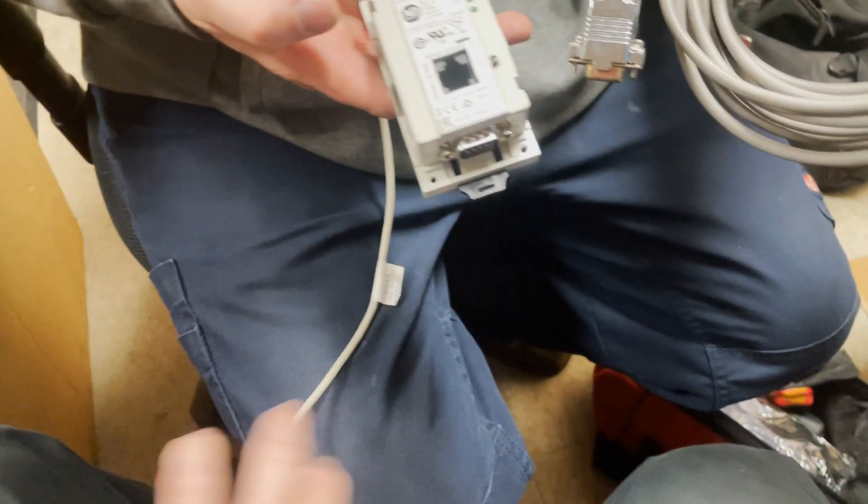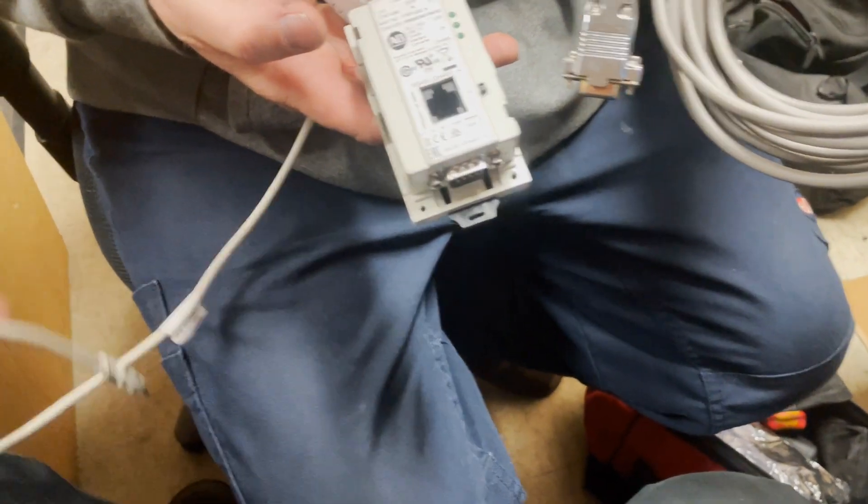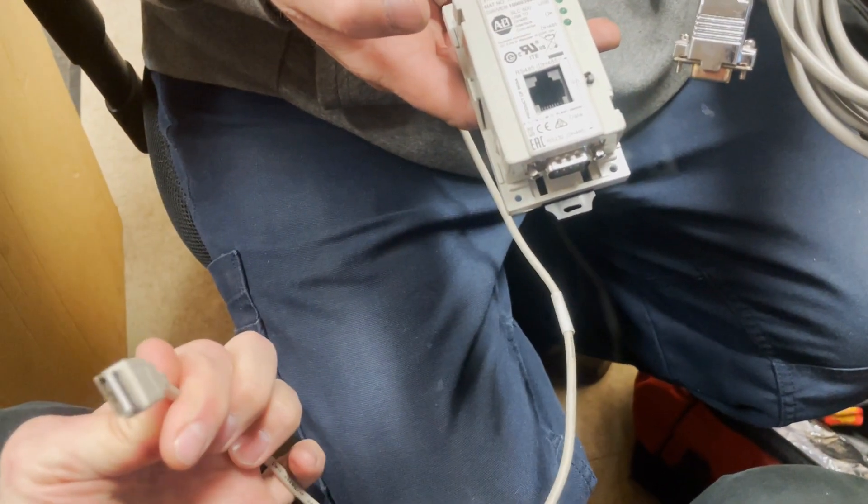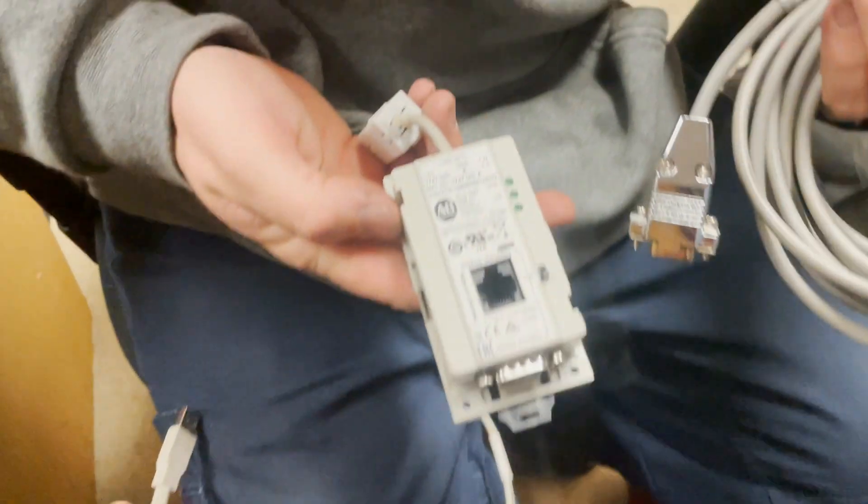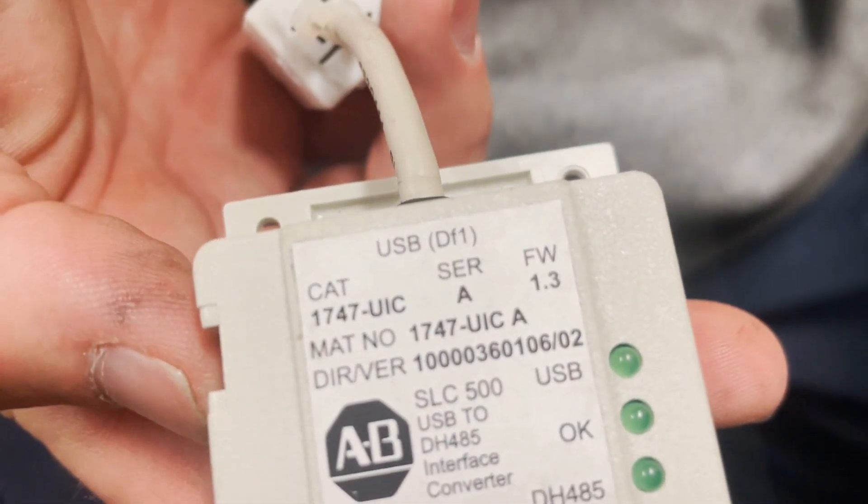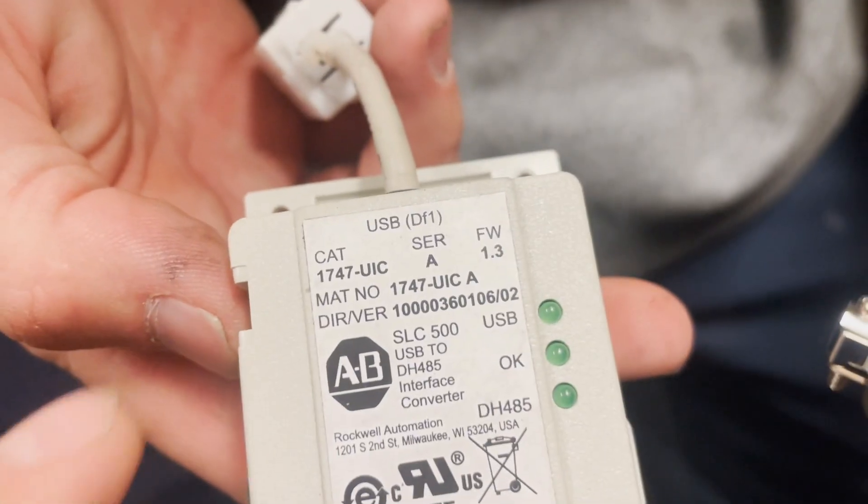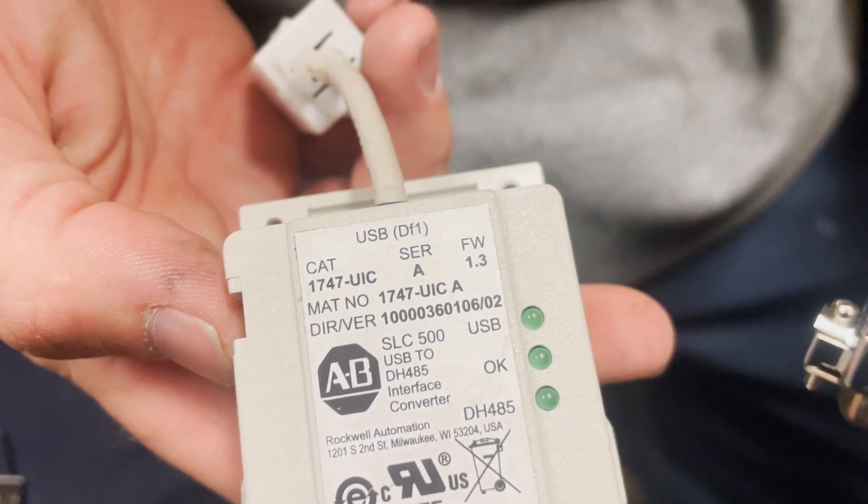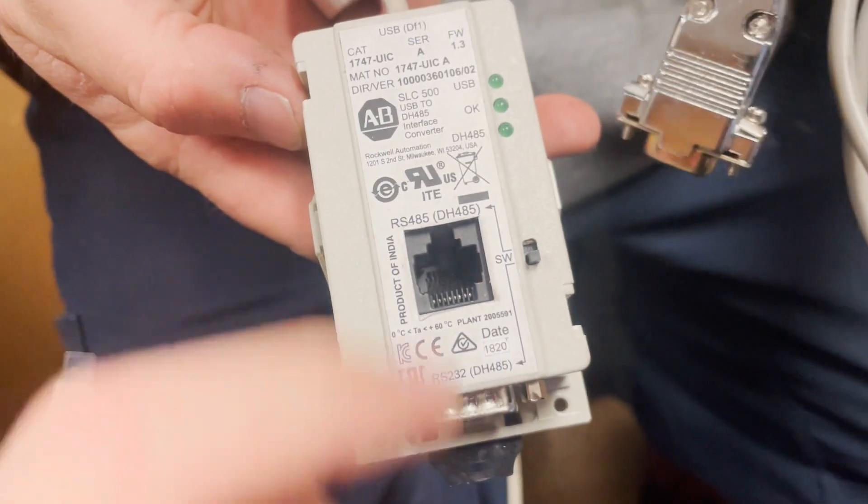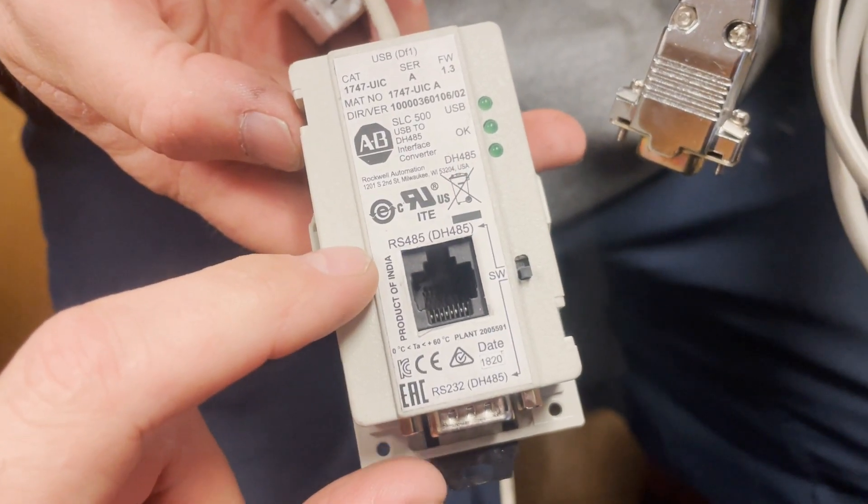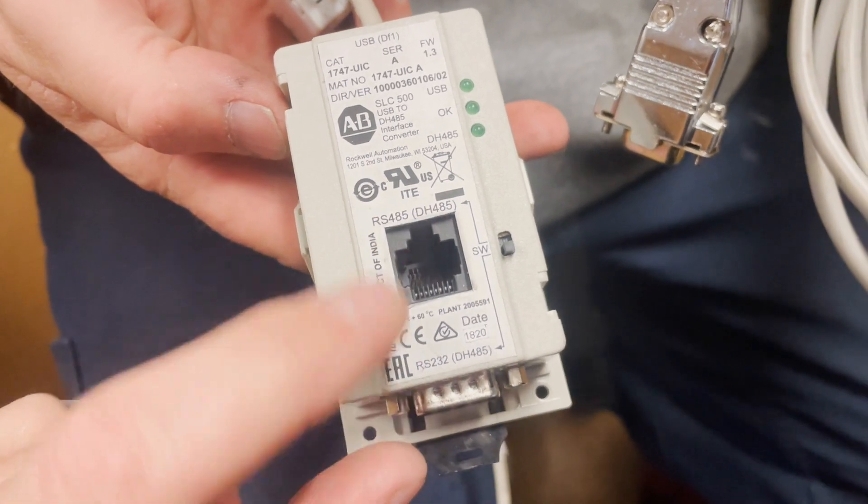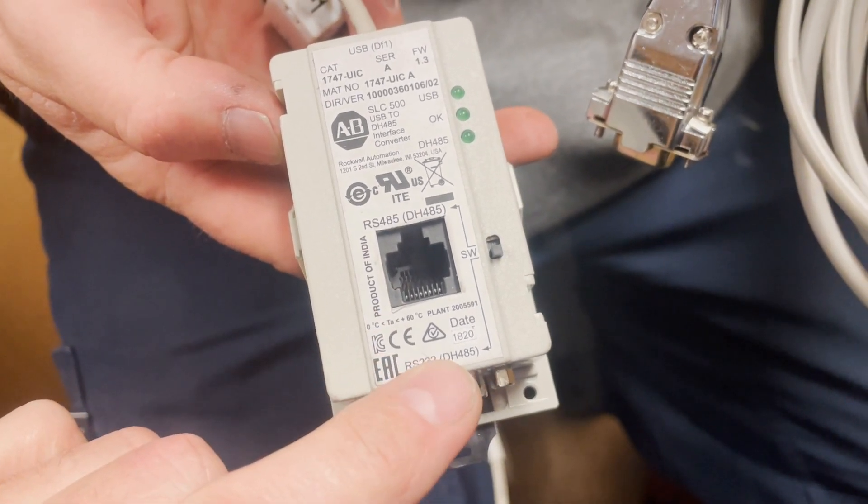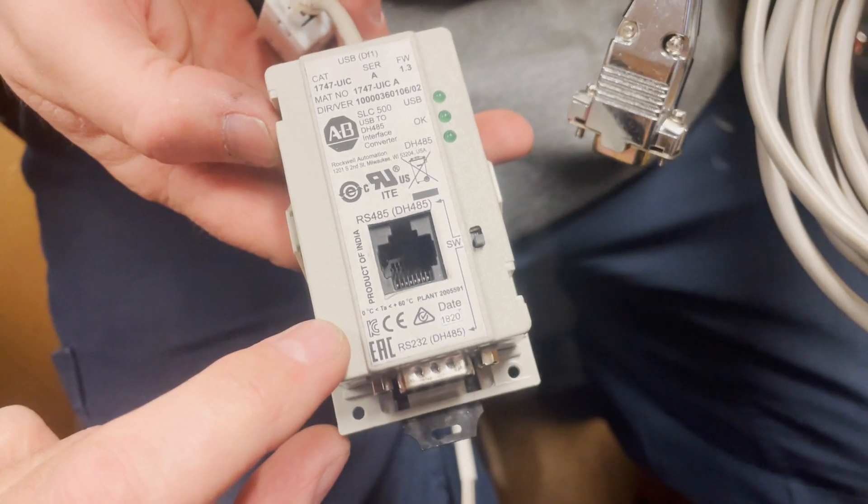The adapter we're using is a USB adapter. It's hard to get these now - I had to custom order this one from Allen Bradley a while ago. It's a 1747 UIC, and this one can do either RS-485 DH-485 or RS-232 DH-485. You'll need this adapter.